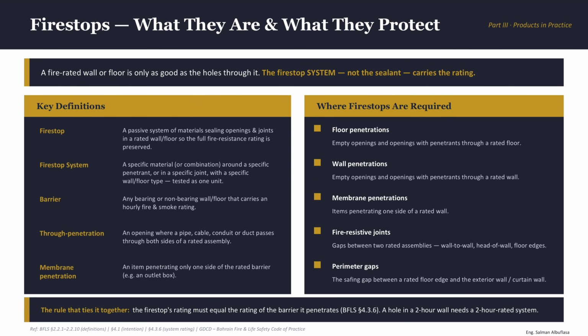This is one of the most overlooked parts of fire protection and one of the most failed on site. No matter how good your product is, something or someone will always do something wrong. To get the idea, let's say you have a 2-hour fire-rated wall, you tested it, you certified it, approved it and installed it. And then at the end of the project, the electrician comes along and drills a hole through that and runs a cable. And then the plumber comes in and puts a pipe through that hole, and then the air conditioning guy passes a duct through it. Each one of these holes is now a path for fire and smoke to pass through that wall. And technically, you no longer have a 2-hour fire-rated wall, now you have a wall with holes in it. That's it. No rating.